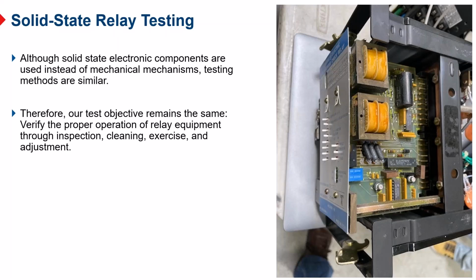So all those things together, in the late 70s, maybe the 80s, the IEEE Power System Relay Committee brought out a bunch of standards called C37.90, C37.90.1, .2. Those set hardware standards for electromagnetic immunity, electromagnetic emissions, HIPOT, which is basically a high voltage dielectric test, and SWC, a fast transient test, kind of simulating a lightning strike in the yard.